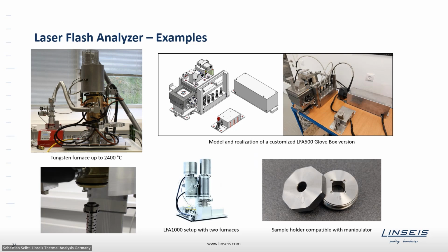application. Here, the special part is that the system is equipped with two furnaces, so that one can cover two different temperature ranges, and one can benefit of the different advantages of a furnace. For example, some allow a very high heating rate or just very high temperatures, and with that you can also maximize the throughput.